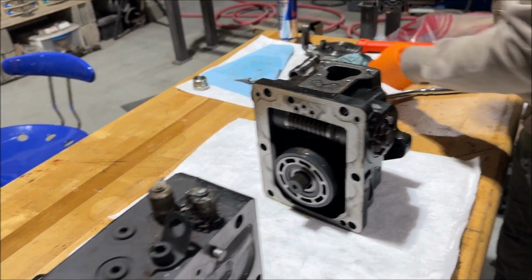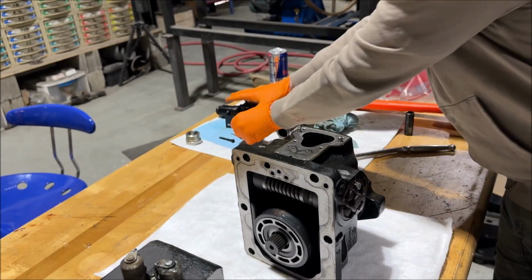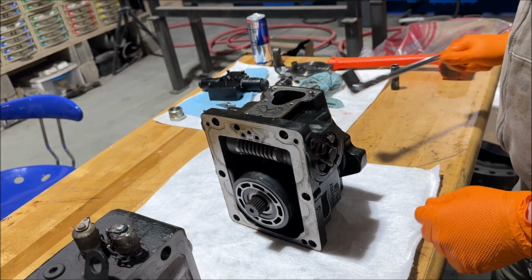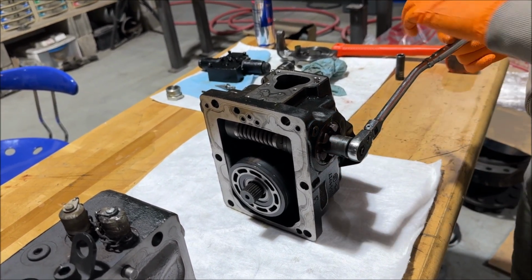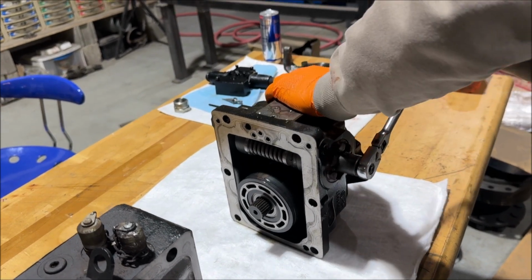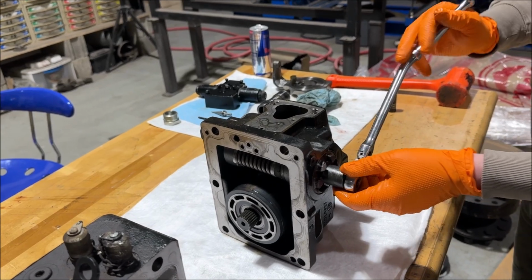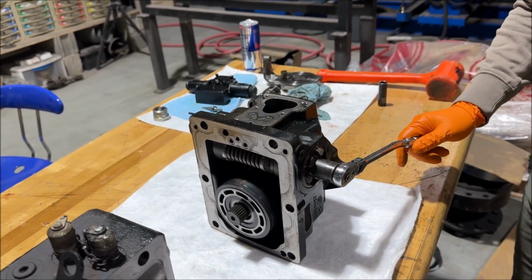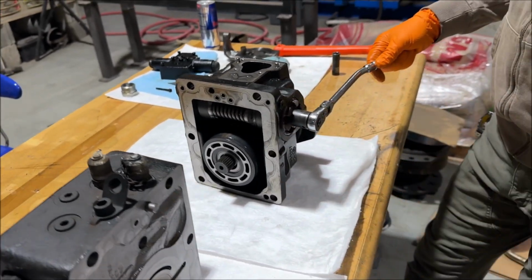Okay. These pumps are made by Danfoss. They are sometimes available on eBay. Wouldn't count on it though. The exact same part number. Yeah. And there's a part in these that keeps failing, and they keep improving it, and it keeps failing. Every time they come up with a part, they have a rev number on the part, and we're up to rev number I don't know what on the new yoke. Do you know what it is?